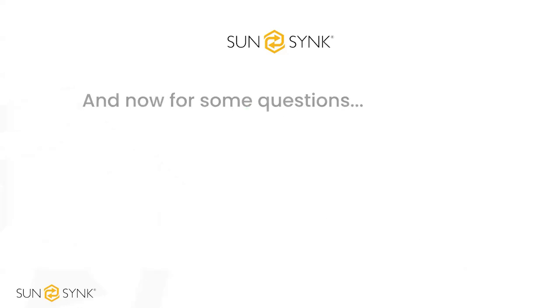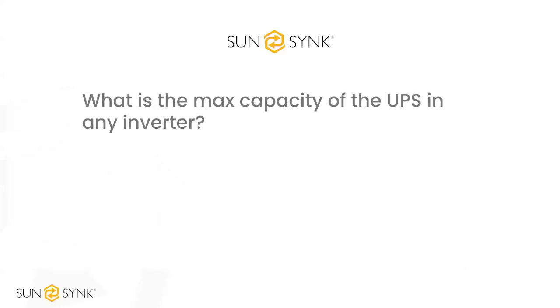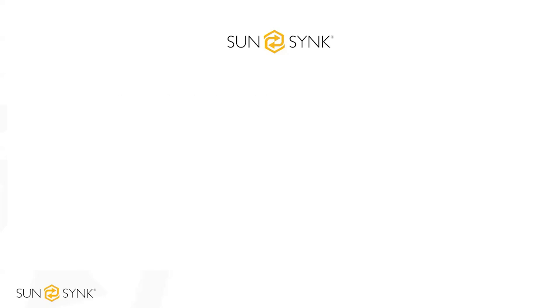What is the max capacity of the UPS in any inverter? The max output on the UPS port is the rated value of the inverter. So if you've got a 5 kilowatt inverter, the max output is 5. Likewise, if you've got a 12 kilowatt single phase inverter, the max output is going to be 12.